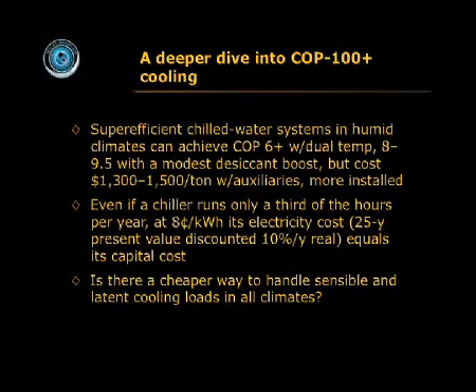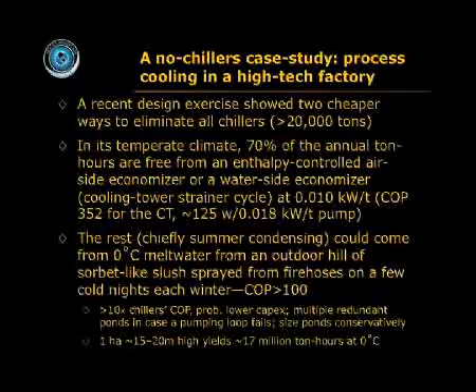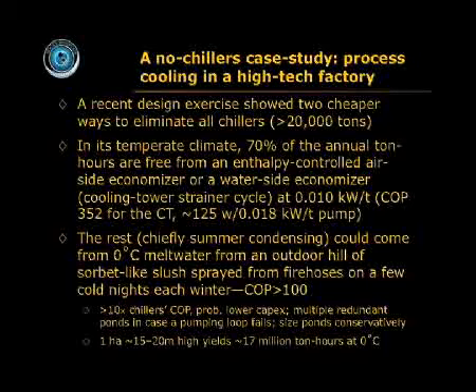And actually, even if your chiller only ran a third of the hours and you only paid 8 US cents a kilowatt hour, its electricity cost would still match its CapEx. So is there a cheaper way to handle sensible and latent load even in a tough climate like this? Well, I'll give you a couple of examples. We recently had a high-tech factory where we were able to eliminate all 22,000 tons of chillers.